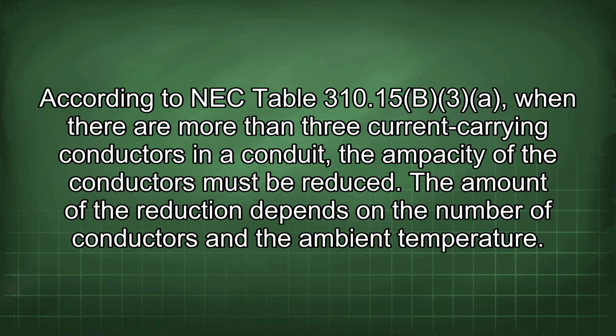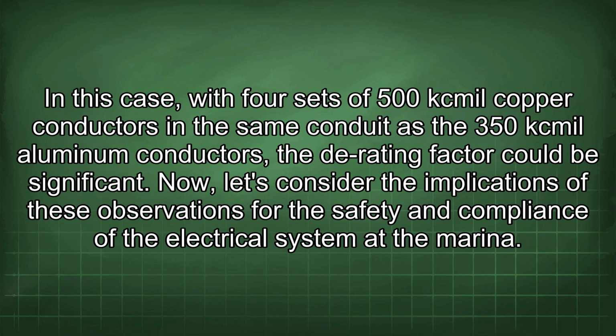According to NEC Table 310.15(B)(3), when there are more than 3 current-carrying conductors in a conduit, the ampacity of the conductors must be reduced. The amount of the reduction depends on the number of conductors and the ambient temperature. In this case, with 4 sets of 500 kcmil copper conductors in the same conduit as the 350 kcmil aluminum conductors, the derating factor could be significant.